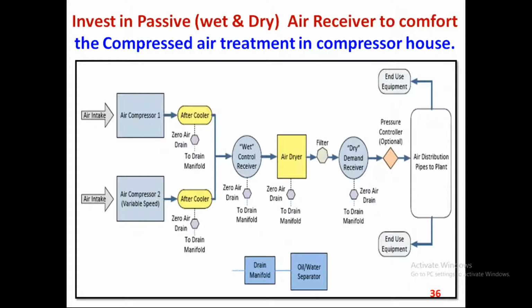This is mandatory. It is from the air best practices guidelines only. This is very much available in all of them. The compressor OEM always suggests you don't go for two receivers. They have stated that the efficiency of the compressor is excellent, but they always find a loophole in going for only a single receiver at the compressor house. It is a loss to the industry. You definitely need to have two receivers in the industry.